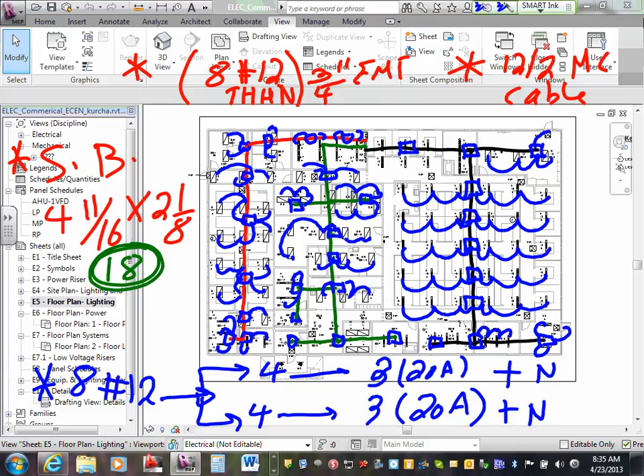So if you want to know how many conduits you need, guys, all you have to do is take the number of circuits you have and divide it by 6. In this case, we have 24. We could have added actually a 4th one. 24 divided by 6 will give you 4 conduits, 4 conduits to move all these circuits through the ceiling. Okay, so I decided to go with 3, a little bit less, because I can group more.